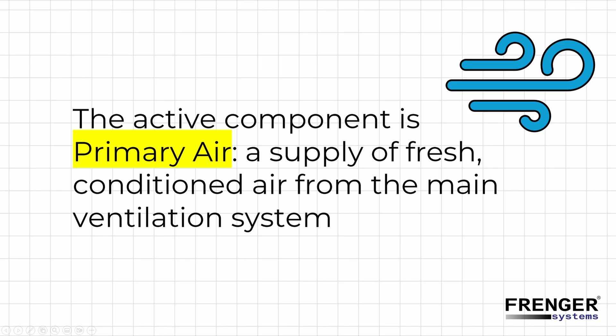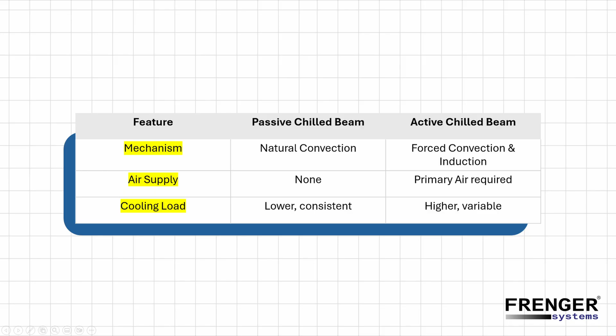This table really lays it out nicely. Your passive beams are all about that gentle, natural convection, which is perfect for spaces with pretty steady, low heat loads. But active beams use that primary air to create forced convection, and this really powerful effect we call induction. That makes them absolute workhorses for dynamic spaces, like offices or hospitals, where the cooling needs can spike up and down all day.